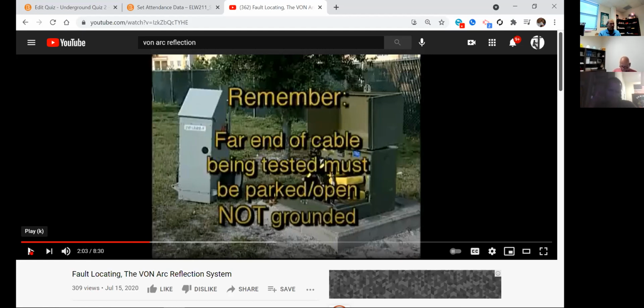All right, so when we looked at that enclosure, remember it was a normal open point, right? And the wires that came in on the bottom went into a lightning arrestor. That is parking. The cable's not feeding any other direction, it's parked, but it still had a lightning arrestor attached to it. Will that suffice? Suffice for what? Parking. Oh, yeah, that would, because it can't go anywhere. Be careful, gentlemen, be careful. Where can it go to?